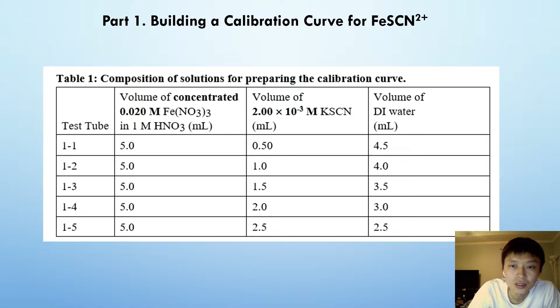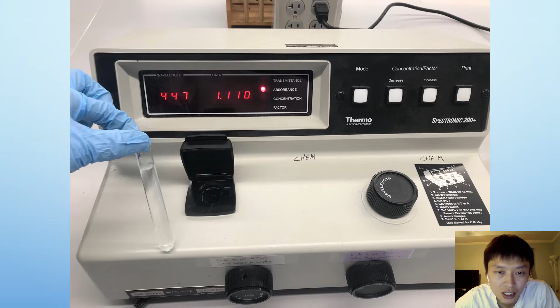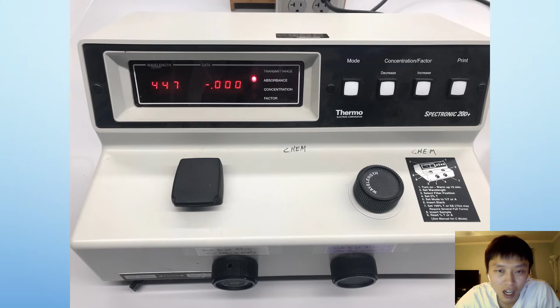So this is a picture I took right during the lab. After I turn on the instrument, I adjust the wavelength to 447, and remember the first step is to calibrate your instrument using a blank, which is DI water. So I put the DI water in, and I adjust the knob to make the absorbance equal to 0.